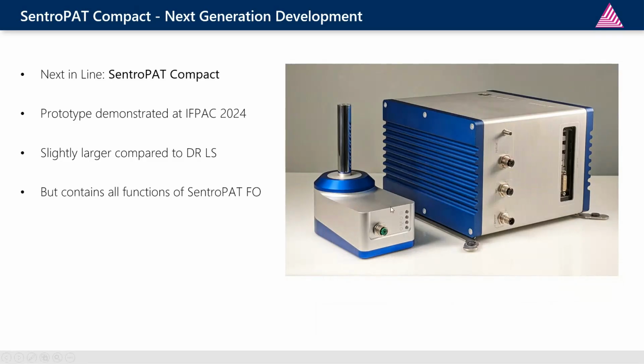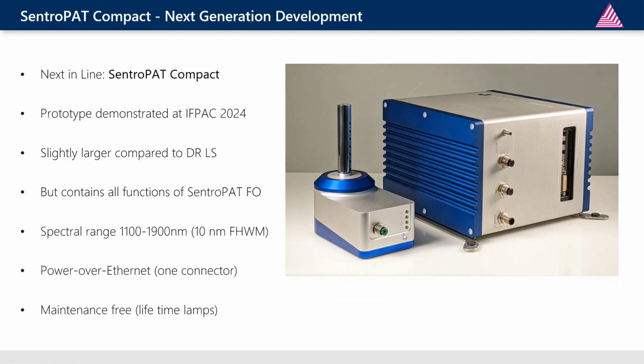You see it's, of course, quite a compact system and still contains the functions of the SentroPAT FO. So that has about the same core functionality. Just the internal embedded computer is smaller. It's running a Linux operating system, and the spectral range is 1100 to 1900 nanometer with a decent 10 nanometer full width half maximum spectral resolution, which from our experience is quite a good spectral resolution for the requirements of resolving as much as possible from the API concentration in a blend.